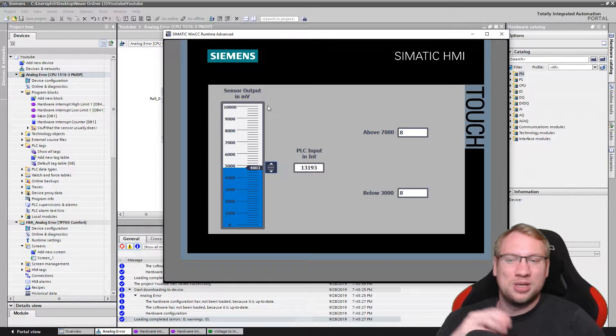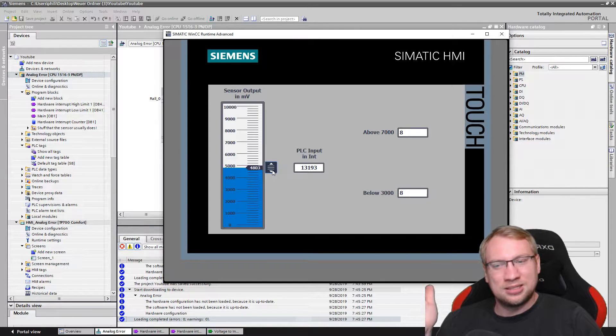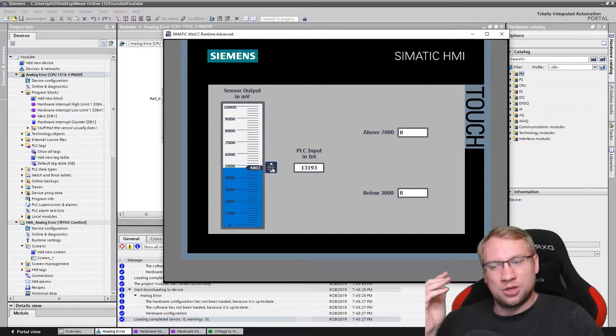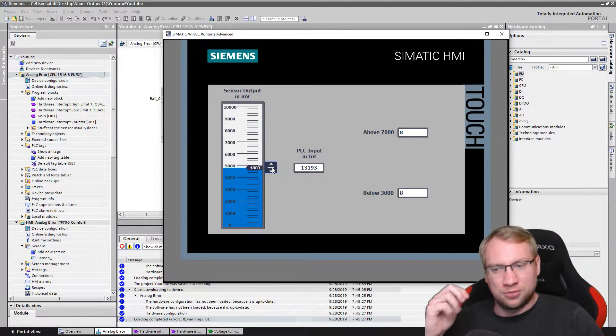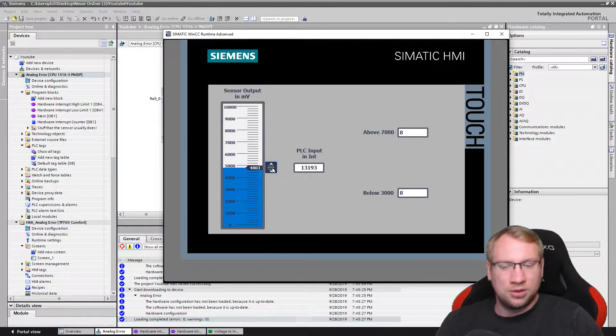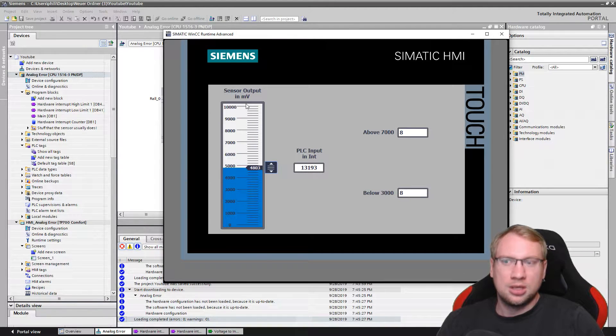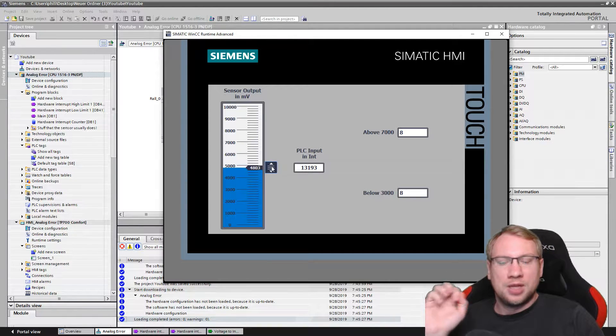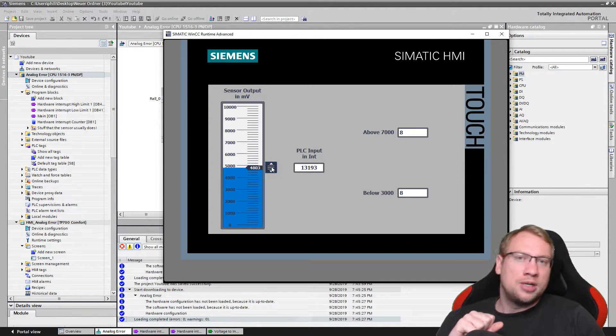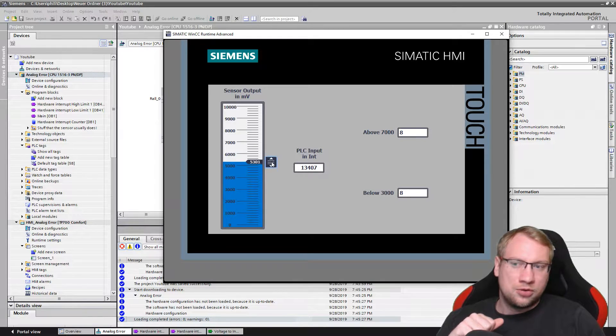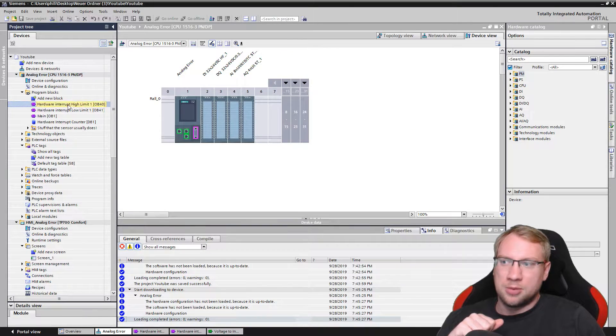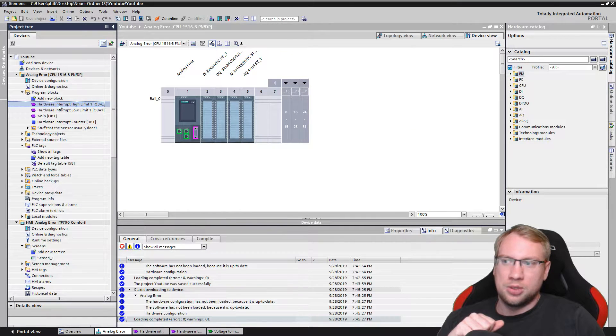I have configured my hardware, my analog input module, in such a way that it realizes and works with values from 0 to 10 volts, which is 0 to 10,000 millivolts. And I have already two hardware interrupts integrated in my program here: hardware interrupt high limit one and hardware interrupt low limit one.